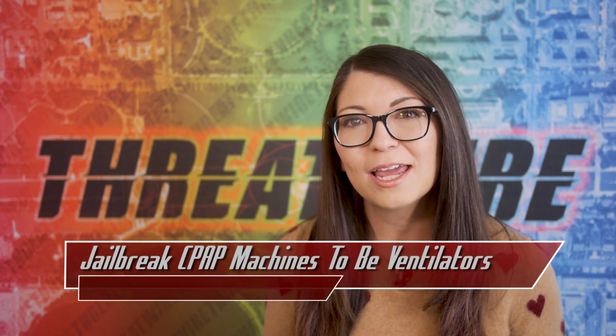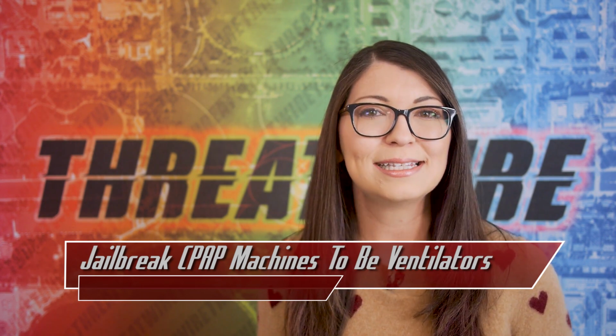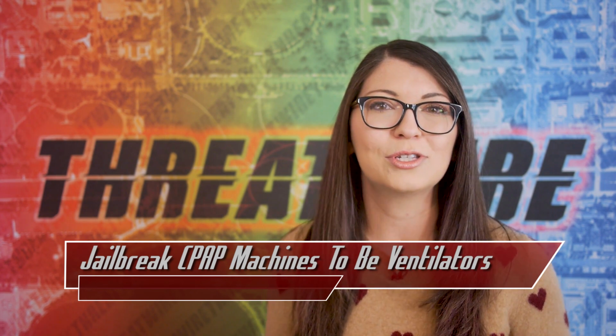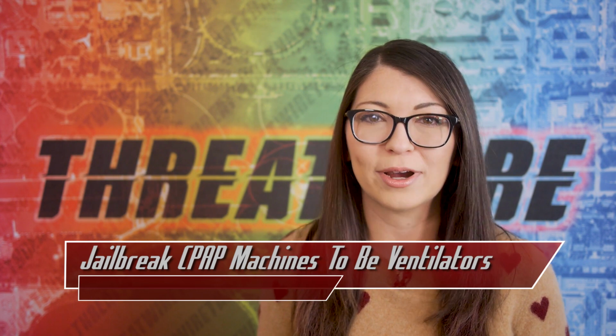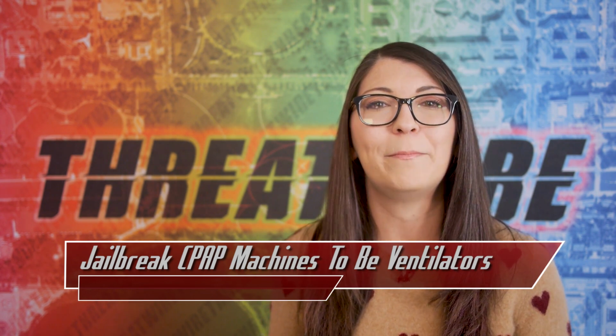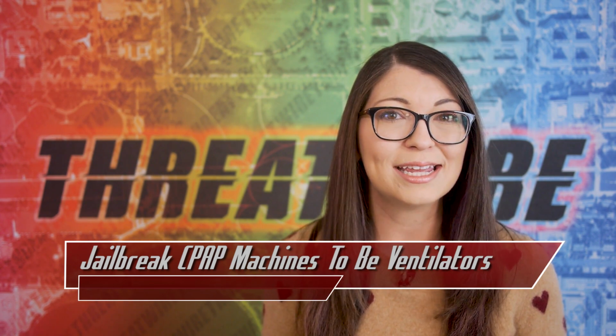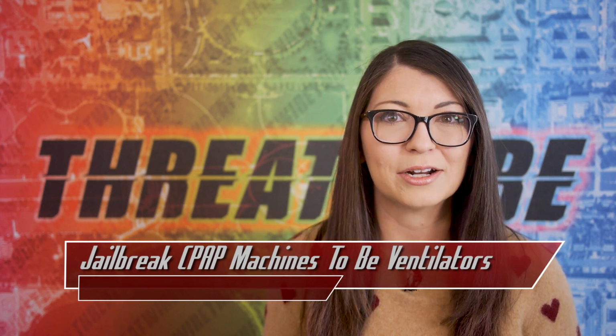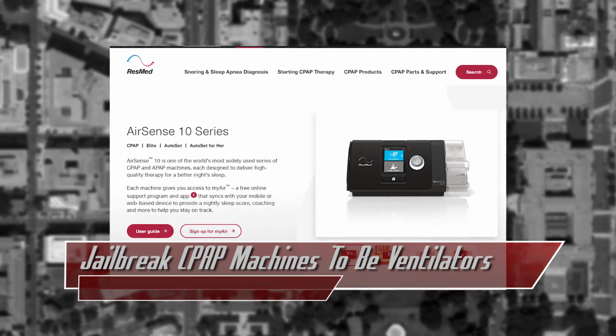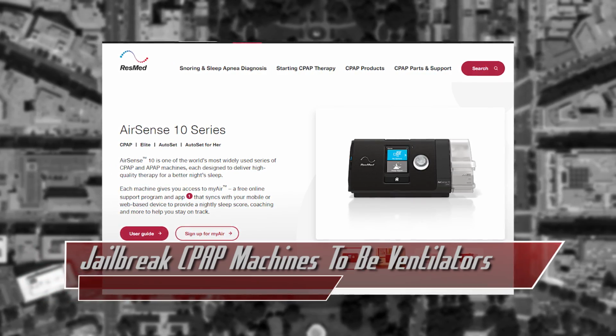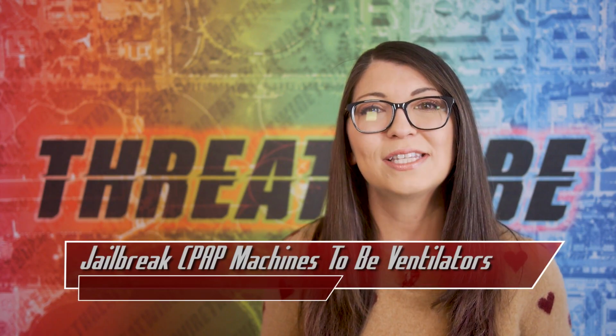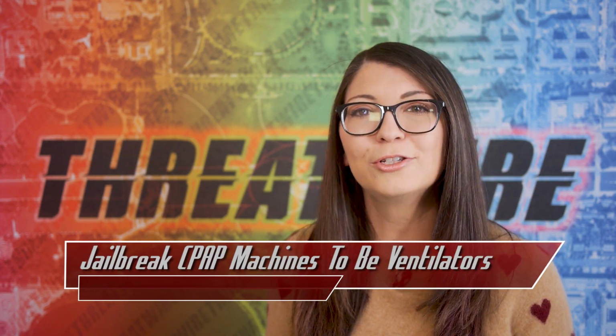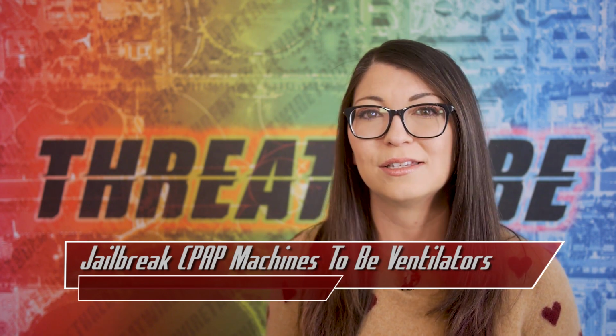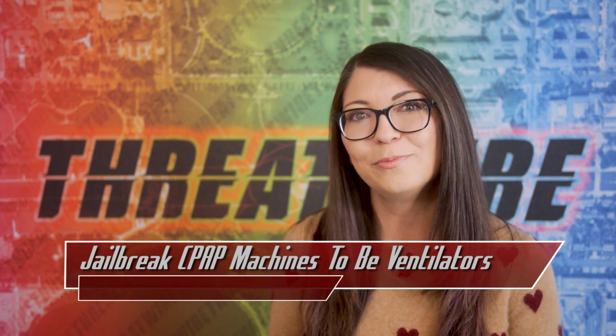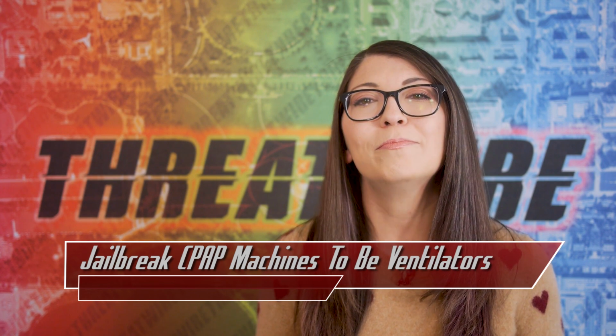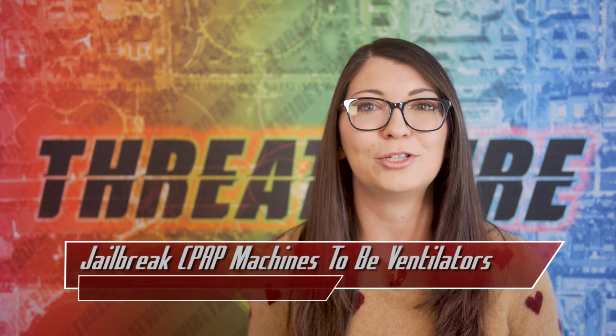He was successfully able to jailbreak a device called an AirSense 10 to unlock its potential to be a bi-level positive airway pressure machine, also called a BiPAP for short, and possibly use this as a ventilator. The company behind these $700 sleep apnea CPAP devices is called ResMed, and they have stated that the AirSense 10 would need a major reworking to function as a ventilator. This company also manufactures ventilators, which are much more expensive than these CPAP machines.